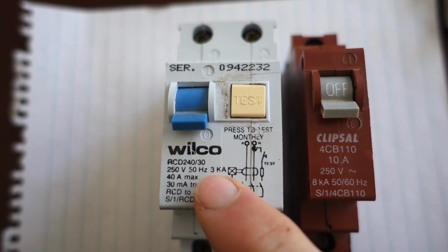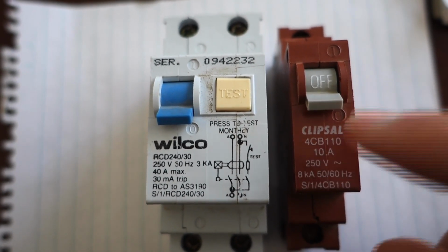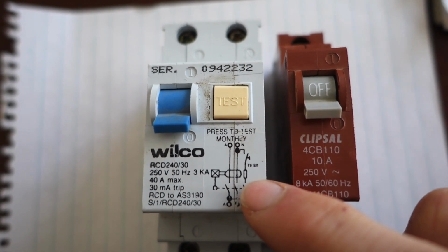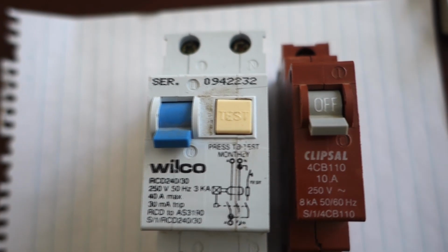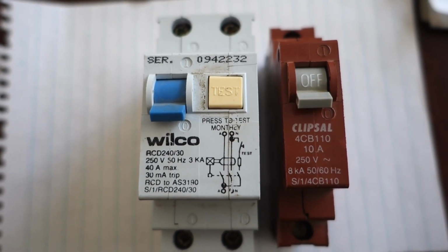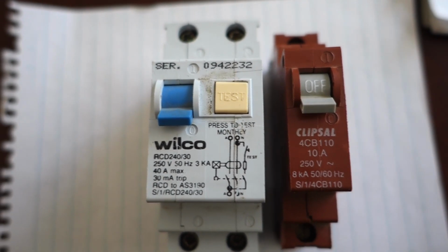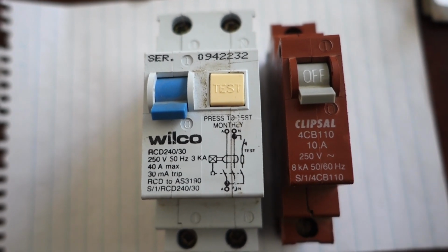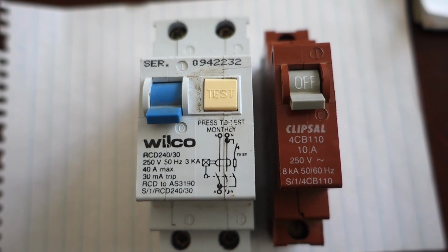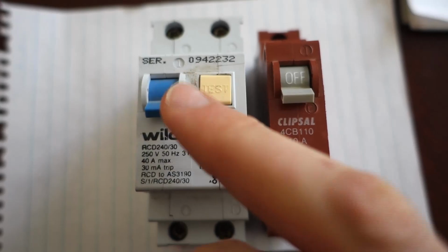So what this guy is going to do, power is going to come through the safety switch into the circuit breaker, out to the lighting in your house and come back. And if it picks up any difference, a 30 milliamp difference, it's going to trip that safety switch. Now this is important because that difference means the same amount of power going out isn't coming back. So what that could mean is the power might be going into something like you or a loved one if they're coming into contact with active wiring or something like that. So it's very important that trips.